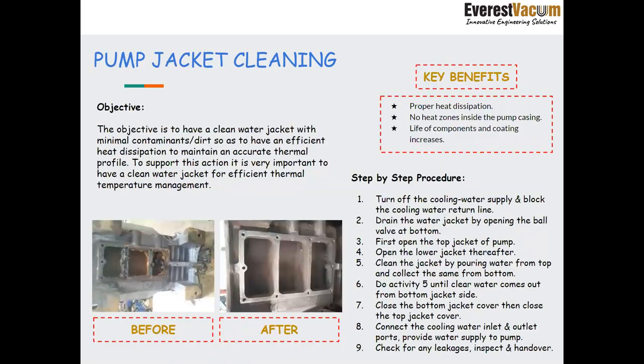Another cleaning operation is for the pump jacket. As we all know, these dry screw vacuum pumps have a cooling water jacket, which ensures that the heat is dissipated properly. There are no localized heat zones inside the pump casing, which ultimately leads to an increase in the life of components and coating. So the objective is to have a clean water jacket with minimal contaminants and dirt, so as to have efficient heat dissipation to maintain an accurate thermal profile.